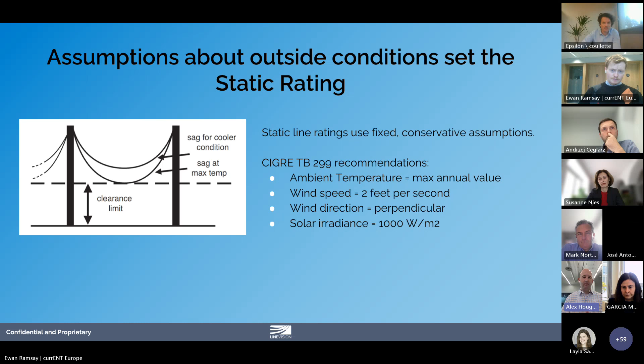You have to assume that it's very hot out. You have to assume that there's very little wind. And when you do that, you are necessarily setting a limit on how much power can be moved. And that limit, if it's too conservative, really prevents operators from having the full degree of flexibility that they could if they actually knew what was happening out there. If they actually knew how much power they could move, then they would have that flexibility. And that's exactly what dynamic line ratings do. Next slide.